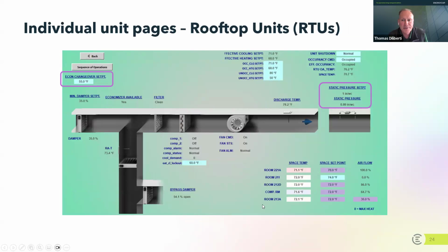A couple other things in this screen that are new, this idea of a static pressure set point. So here it's giving you this set point. So this is the command, this is the status. Notice these things are very close, almost 1 and 1. So that says the system is working the way it's supposed to. We haven't really seen that before. And this is unique too on this one here.